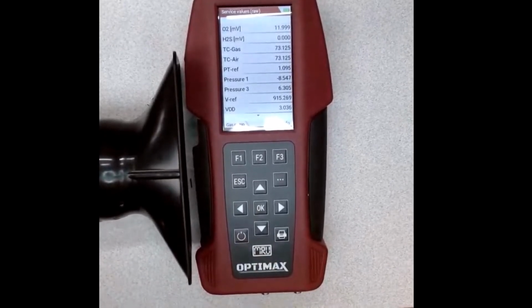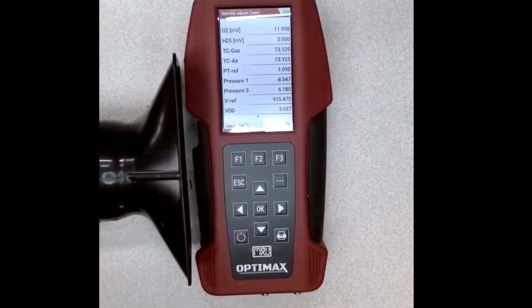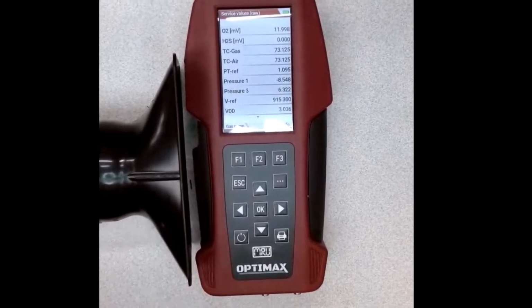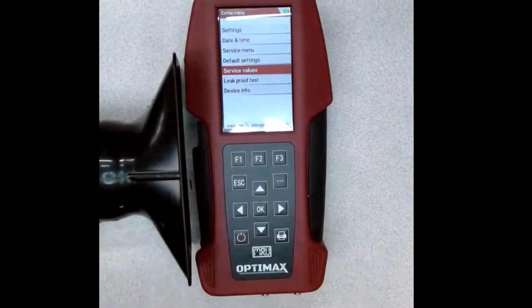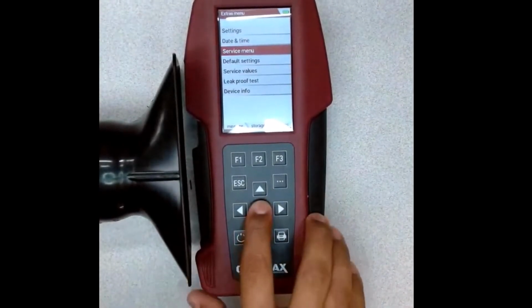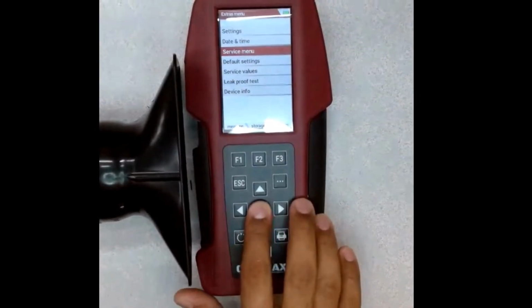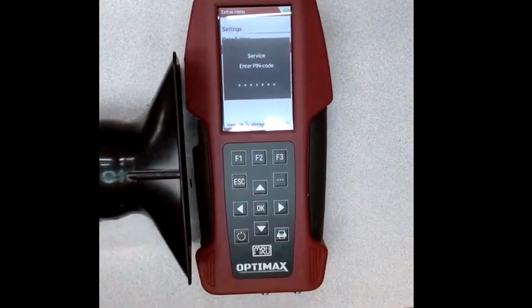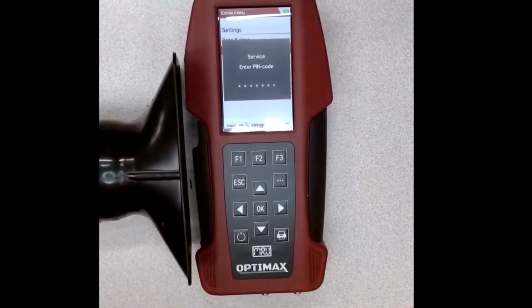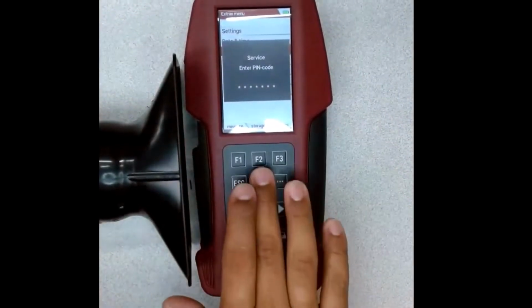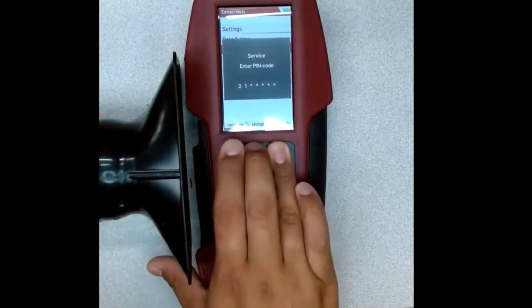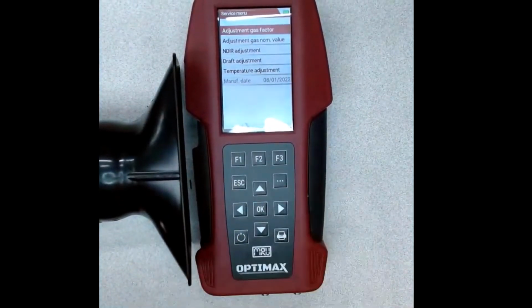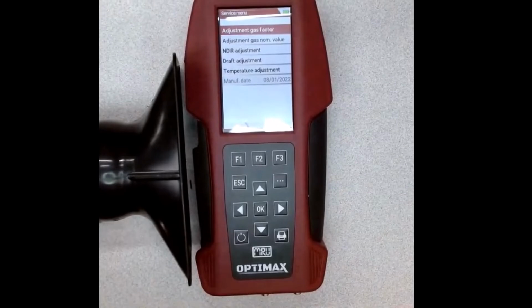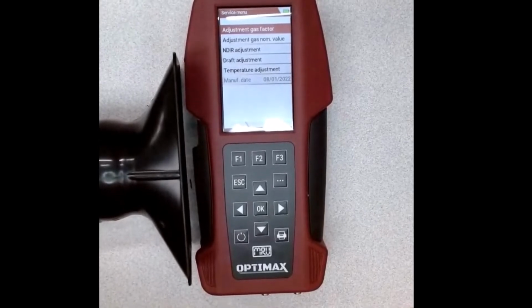Once the analyzer has run for several minutes, we want to put the analyzer into service mode. In order to do that, we'll escape out of the service values menu, and we'll navigate up to the service menu. From here, it'll ask for a service pin code whenever we try to enter this menu. To enter the service menu, we just enter the service code. And this will be specific to each analyzer for a calendar year, and we can essentially give a code for any analyzer to be serviced, but it'll be specific to that analyzer.